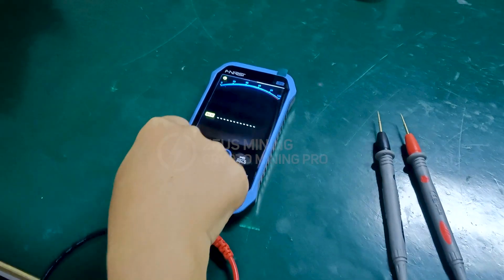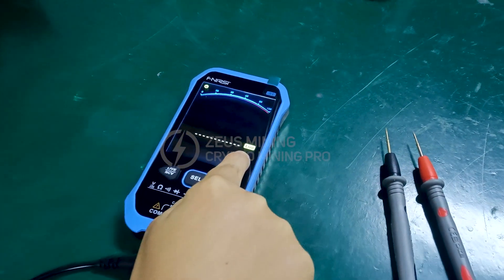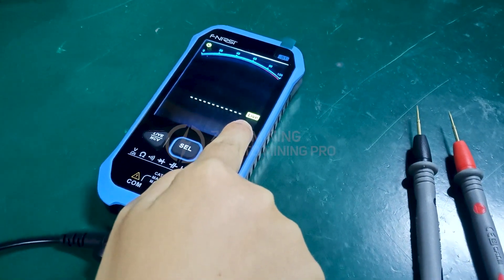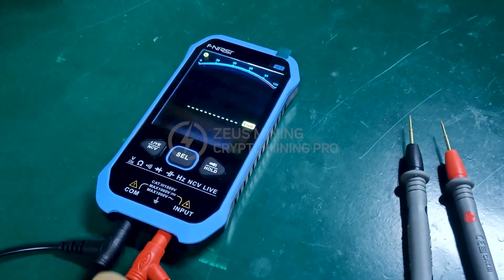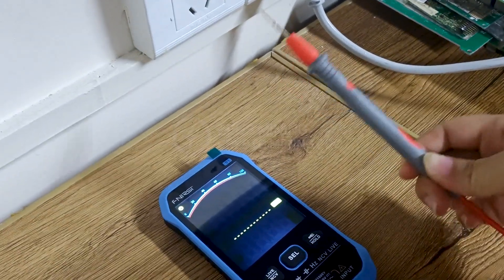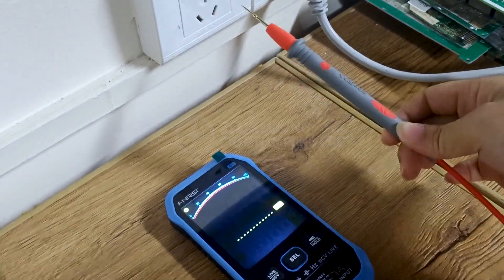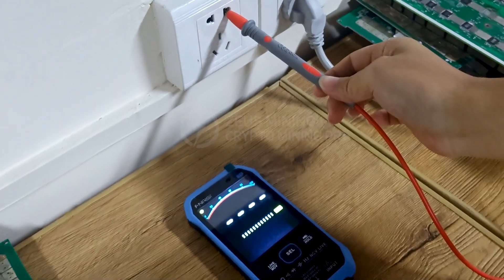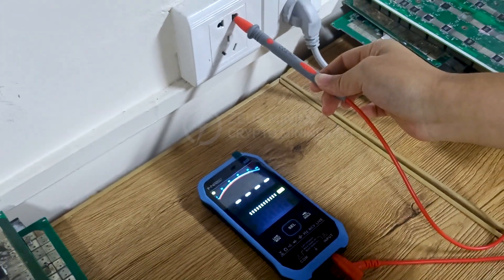Press the left button again and LIVE will be displayed on the right side of the screen. It can test the live wire and the neutral wire. At this time we only need this red test probe. Insert it into the socket. When we hear a beeping sound, it means it's the live wire. However, this hole doesn't make a sound, indicating it's the neutral wire.